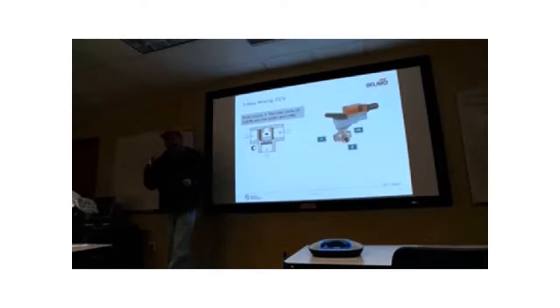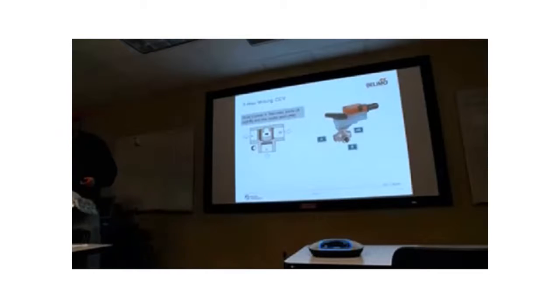Here's the most important thing about what I'm seeing here now. I'll give you the scenario. New construction. You guys don't get involved in new construction so much, but it could be just someone's in there. Say they put a new valve in, right? They put a new 3-way valve in. Fitter goes in, puts the valve in. They take the actuator off first, right? Because you want to spin it in with the pipe wrench. So you take the actuator off, put it in, and then you stick the actuator back on the valve. Now, if you remembered exactly what it looked like when you pulled it off, in fact, that's what I would recommend. I would recommend, however it came off, put it on exactly the same way.